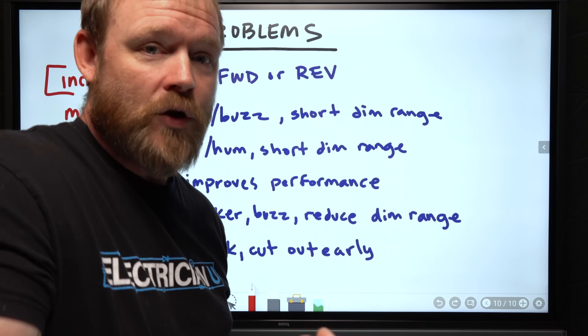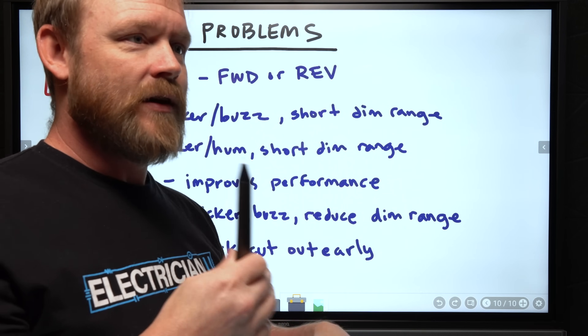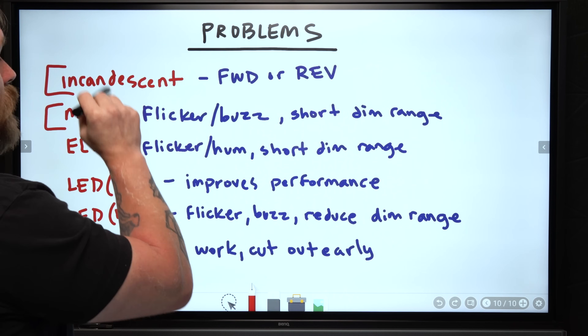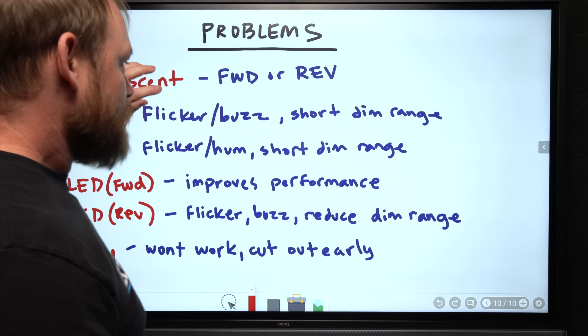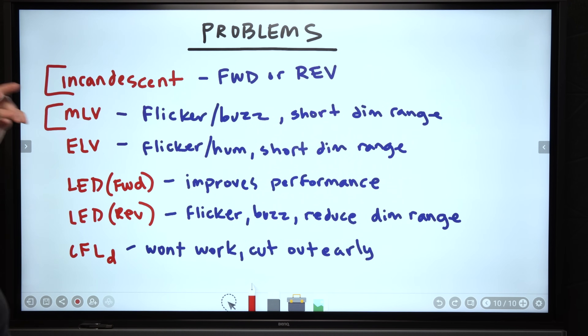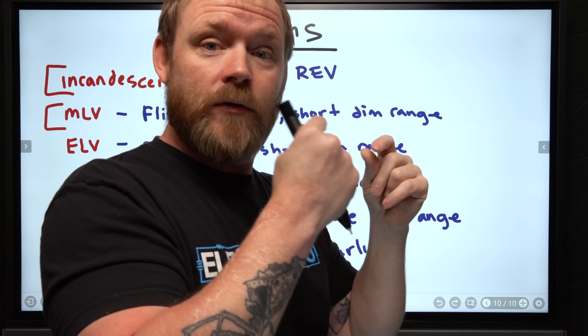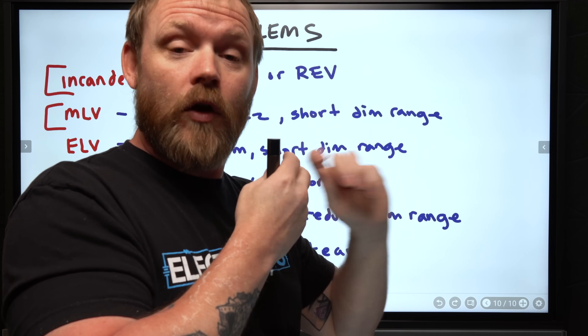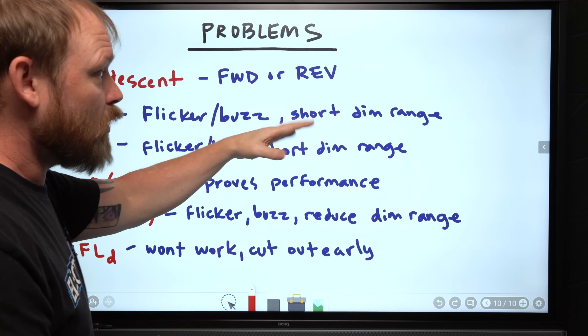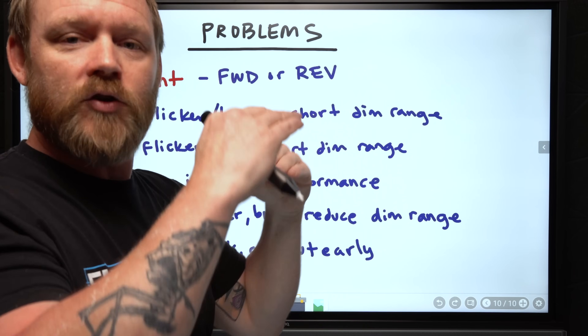Problems by bulb type: incandescent works fine on forward or reverse phase - that's why triacs still work, it doesn't really matter since it's just a resistor changing current. Magnetic low voltage - if you use the wrong phase cutting, you'll probably see flickering, buzzing, or a short dimming range. Electronic low voltage - if you don't get this right, you'll have abrupt state changes that build up over time and develop a hum or flicker, because it's not meant to handle the switching. Both MLV and ELV will likely give you a shortened dimming range.